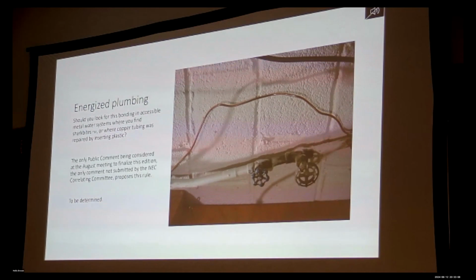Now, what happens if there's a little trickle current or fault, and it won't trip the breaker because it's going to plumbing and it hits that section of PVC? Or that shark bite. Shark bite is one brand that doesn't maintain continuity, and they say so. Some other brands do. Well, here's energized plumbing on top of some shorted equipment that somebody could touch and get zapped. Two ways to get harmed. So maybe you should bond around it where you don't replace the whole water system with plastic, but just put in something that interrupts the continuity.